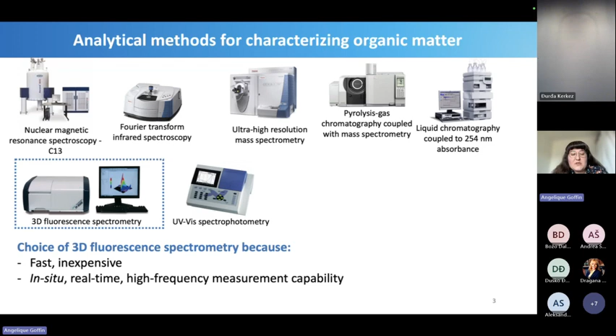So what is this method? Very quickly, this method uses light. You send light at a certain excitation wavelength, a certain level of energy, into the sample, and the sample will react to this light and emit another light, which will be detected by the measuring device. And you will obtain this type of map, which is three-dimensional because you have one dimension with excitation wavelengths, another with emission wavelengths, and the third is the fluorescence intensity. The fluorescence intensity can give you various information. First, the more red it is, the more fluorescence intensity you have, and the colder the color, the less fluorescence intensity you have. So you can have information about the quantity of organic matter you have.